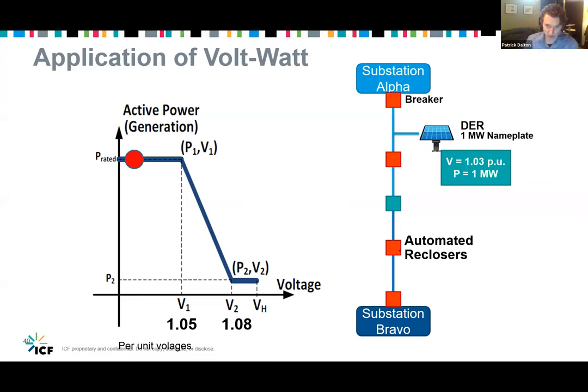And there's a different substation that's tied together. And this is very common, to have distribution field ties for flexibility to operate the system. So thinking back to our voltage impact slide, a DER that's near the substation, there's not as much line for that active power or impedance for that active power to go across and potentially raise the voltage. So much lower chance of having high voltage when the DER is close to the substation, given the conductor is large enough and a number of other items, but that's a bit of a simplification.